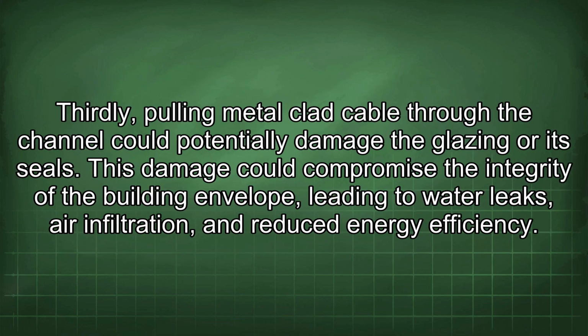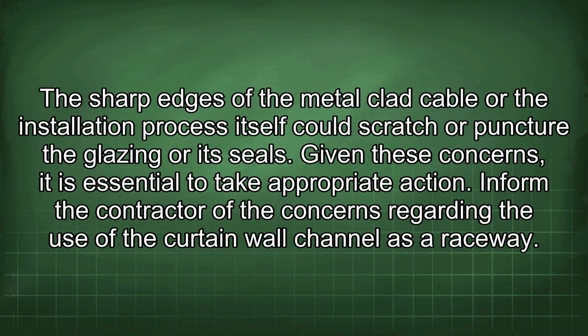Thirdly, pulling metal-clad cable through the channel could potentially damage the glazing or its seals. This damage could compromise the integrity of the building envelope, leading to water leaks, air infiltration, and reduced energy efficiency. The sharp edges of the metal-clad cable or the installation process itself could scratch or puncture the glazing or its seals.